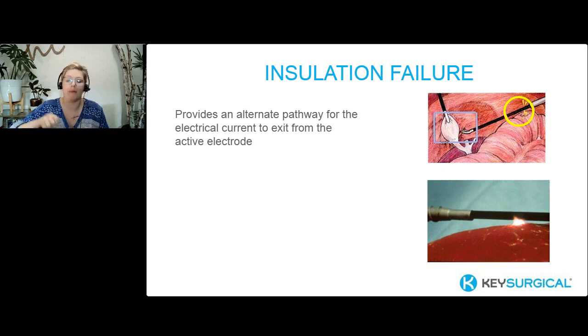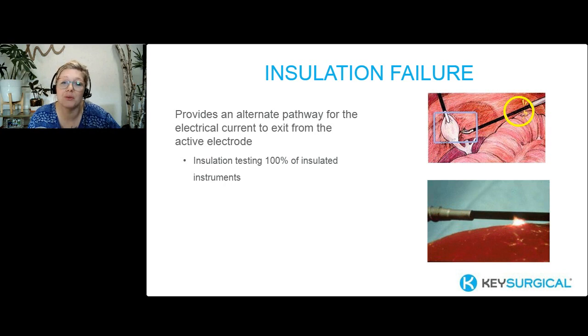We're scraping, we're scratching instruments. An instrument gets dropped on the floor, or just rough handling can damage that insulation. While it's very hardy, it's not free from damage, right? So one of the ways that we can prevent this insulation damage or really work against having these complications is having a great relationship with our sterile processing department and making sure that both of us together understand that 100% of insulated instruments should be evaluated when they go through sterile processing for insulation damage.